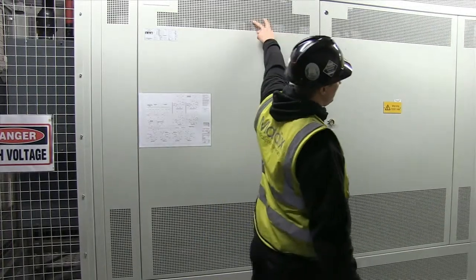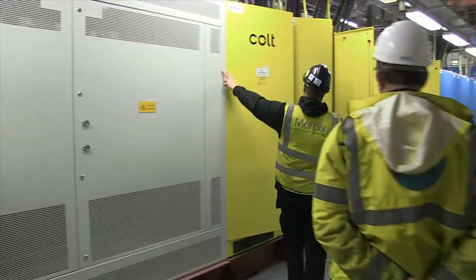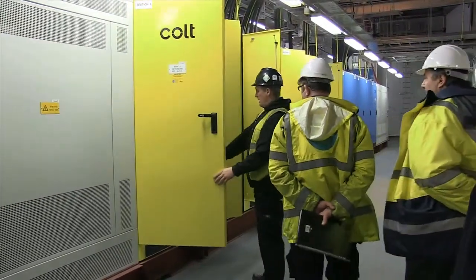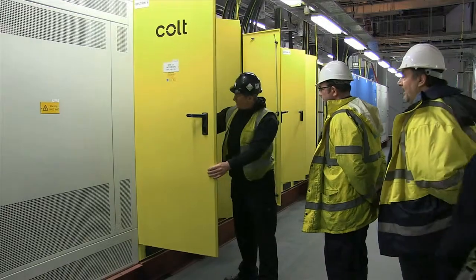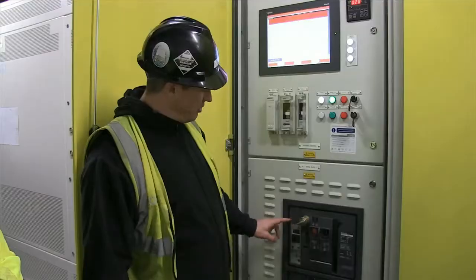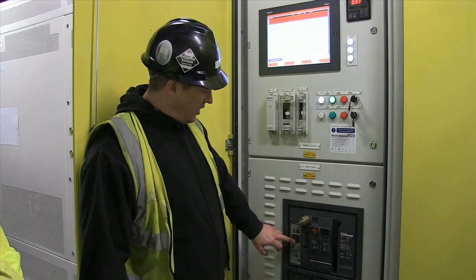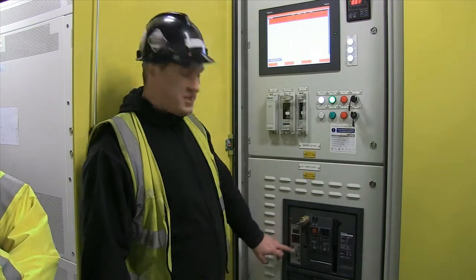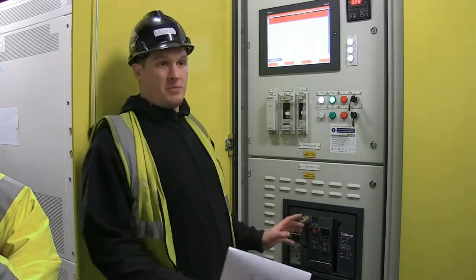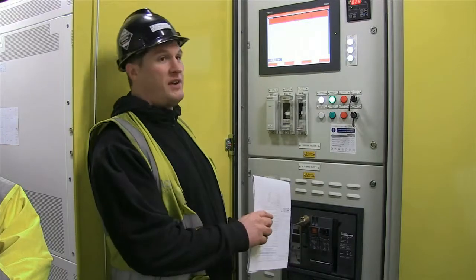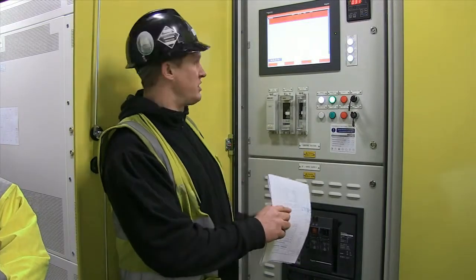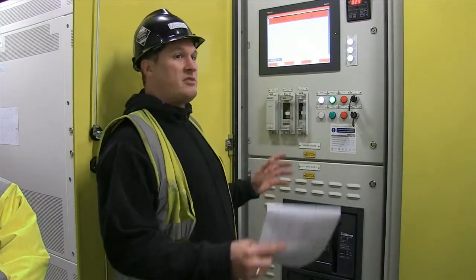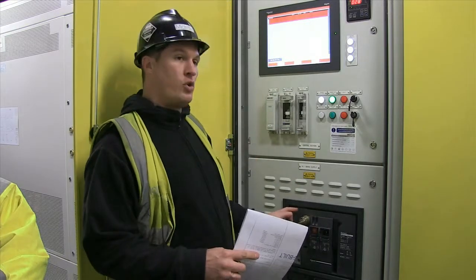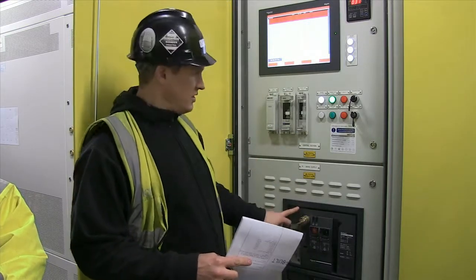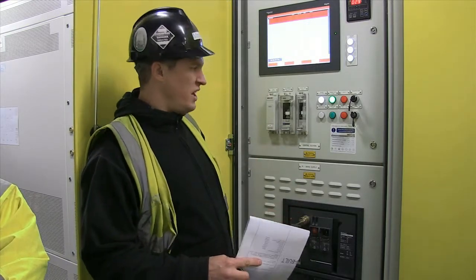Transformer, LV coming out to the breaker. Coming down into the LV mains incomer, which is micrologic, is this reset button. The only thing that can trip that reset button is this micrologic. So if that comes out, there's been a fault on the board, and that will prevent that breaker ever closing. So if any changeovers take place, mains are available again, it still won't close this board because it sees there's a fault. That's the only time that will come out. You just push it in and it will reset it.